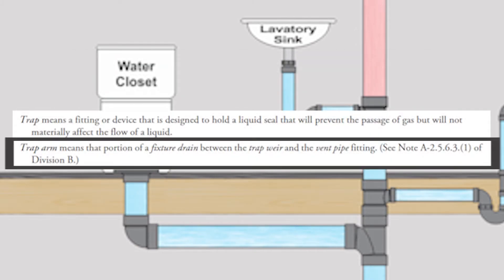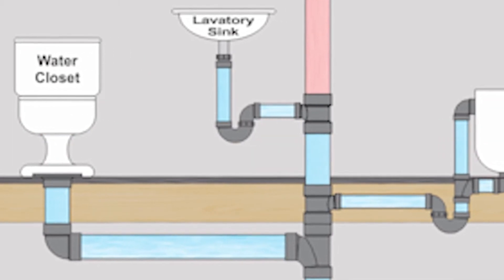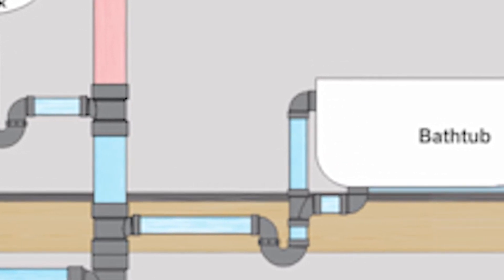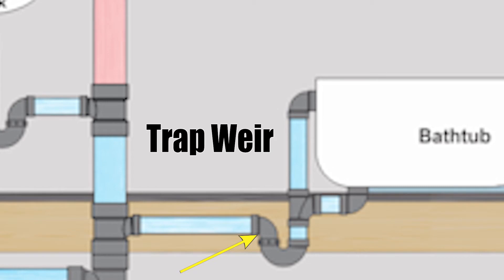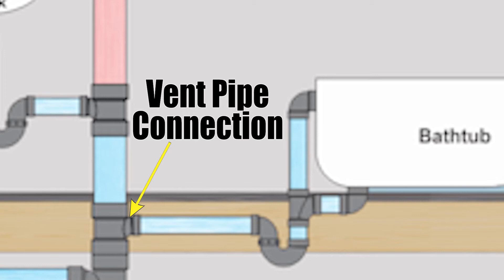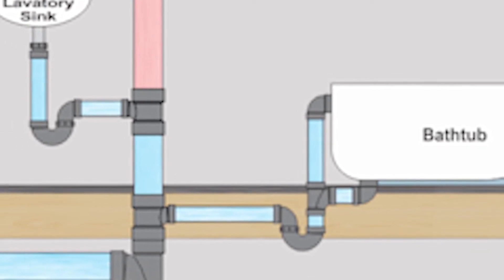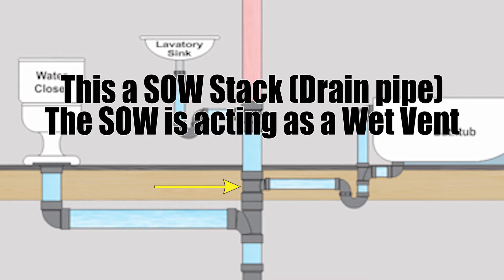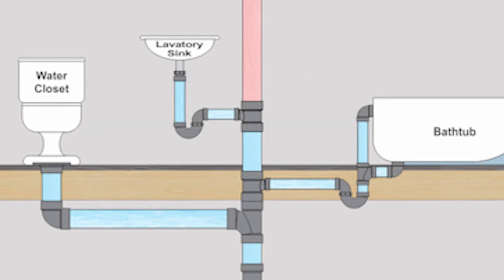The code defines it like this: trap arm means that portion of a fixture drain between the trap weir and the vent pipe fitting. The trap weir is this part of the trap right here, and the vent pipe connection is this tee right here that connects into the soil or waste stack. If you're looking at the toilet and the bathtub, they join into the drain rather than the vent — that's because it's wet vented at that point. Wet venting will be its own video series because it's very involved, so don't worry about that yet.